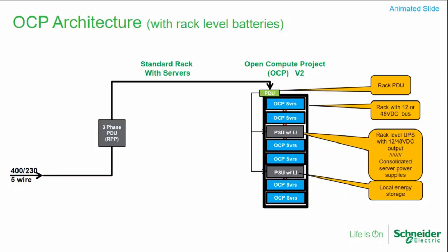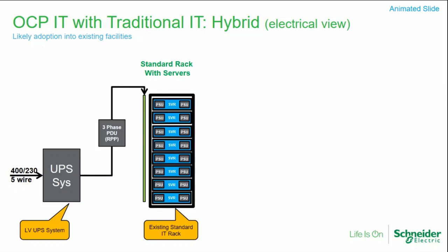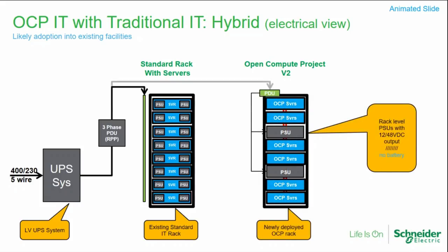When you look at this you have to wonder: is this for everybody? Can everybody deploy this? This looks pretty specialized. Your infrastructure upstream looks streamlined, but not all data centers look like that. What's expected is that if you have a data center with mixed loads — traditional servers with an upstream UPS system — you can still deploy open compute right next to those racks, just without the batteries inside the rack, which is what some enterprises already do. One open compute member like Fidelity who deploys open compute gear does it this way.